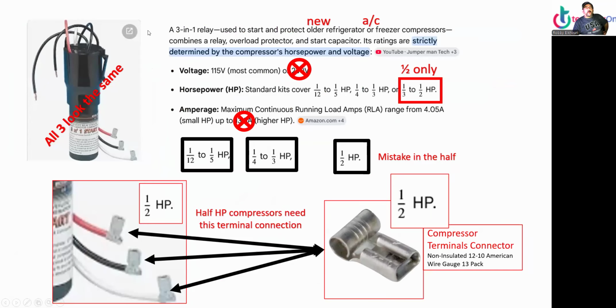All right, now let's talk about the 3-in-1. The 3-in-1 relay is used for start protection on older, not old, on also new refrigeration or freezer, also AC. All right, so many things are wrong here. I Googled it. It's YouTube. Strictly good for compressors by horsepower and voltage. So voltage 115. I've never seen 220. So horsepower: well, they have 3 kinds. The 1/5th, quarter and a third, and only half. All right, and here it shows third to a half. No, only half.